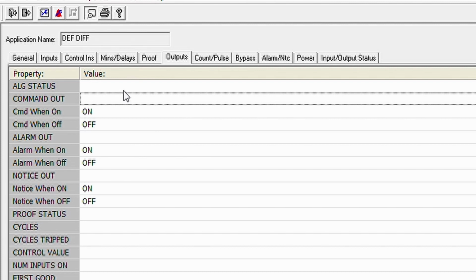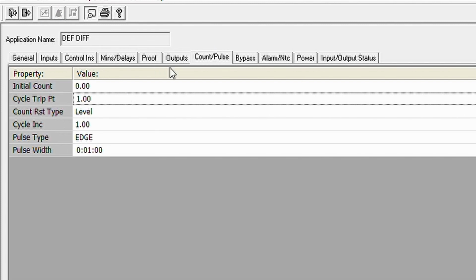You can control board points, you can control other applications. It could be an input to another application. So we'll say you're doing some kind of proofing with it. You could do that. Your counts, your pulses, so your level edge, however you want to do your counting, whether it's on or it's off, or if it goes from off to on, or it's a change of state.